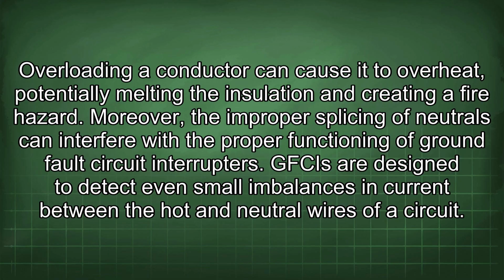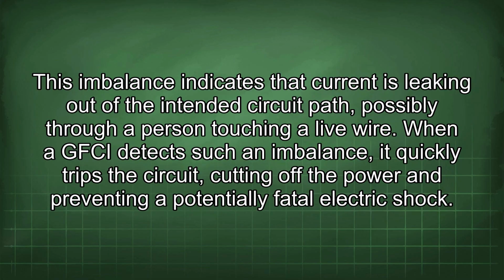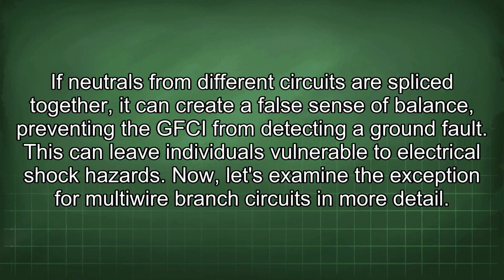Moreover, the improper splicing of neutrals can interfere with the proper functioning of ground fault circuit interrupters. GFCIs are designed to detect even small imbalances in current between the hot and neutral wires of a circuit. This imbalance indicates that current is leaking out of the intended circuit path, possibly through a person touching a live wire. When a GFCI detects such an imbalance, it quickly trips the circuit, cutting off the power and preventing a potentially fatal electric shock. If neutrals from different circuits are spliced together, it can create a false sense of balance, preventing the GFCI from detecting a ground fault. This can leave individuals vulnerable to electrical shock hazards.